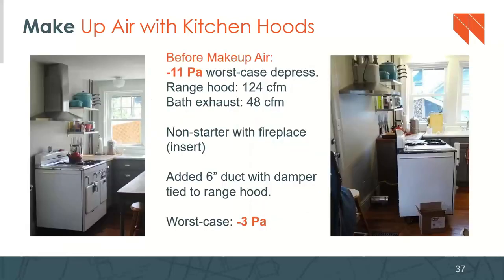So here's an example of a house that's not all that tight, but it was a retrofit home, and it was pursuing LEED for Homes, and they had a wood burning fireplace in the home. So we needed to do makeup air. We needed to do this worst case depressurization testing. Before any makeup air was added, when everything was turned on, the range hood, the bath exhaust, the dryer, it was negative 11 Pascals inside the home. With this fireplace, that's a non-starter. You don't want to have a negative 11 Pascal pressure difference when you have a wood burning fireplace.